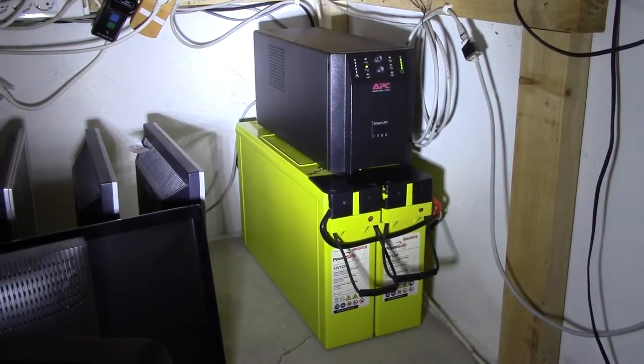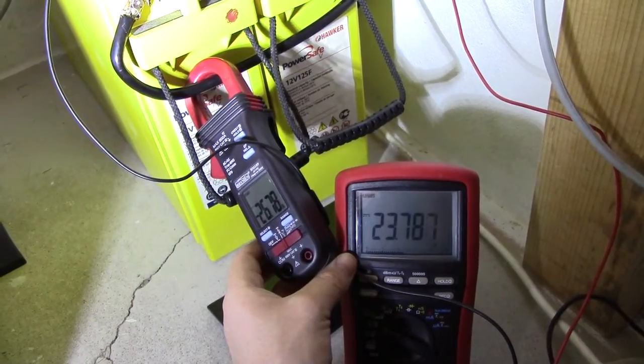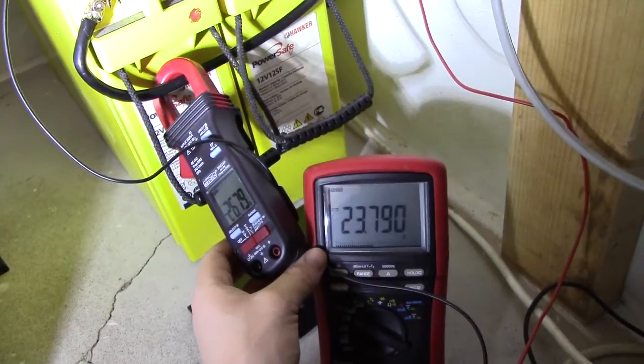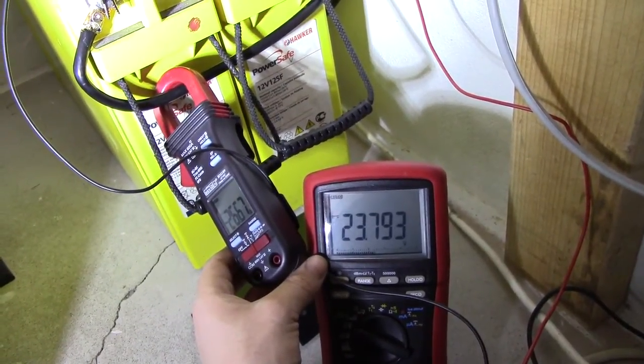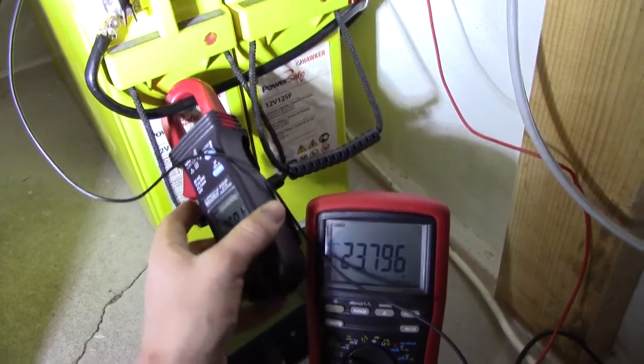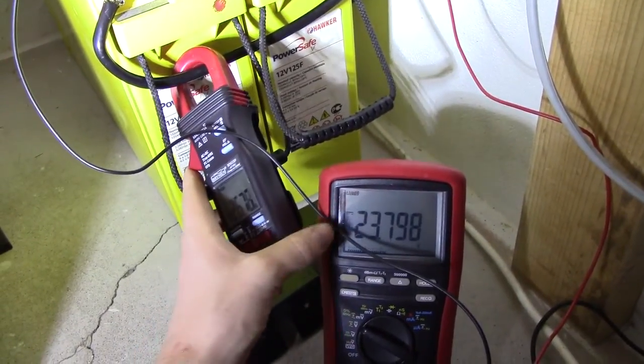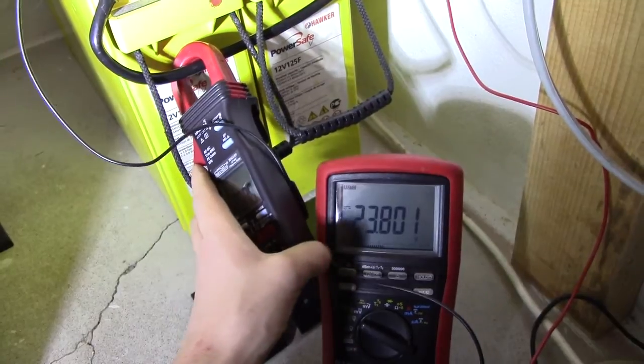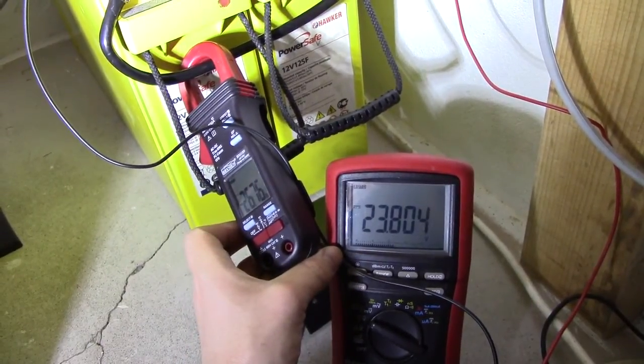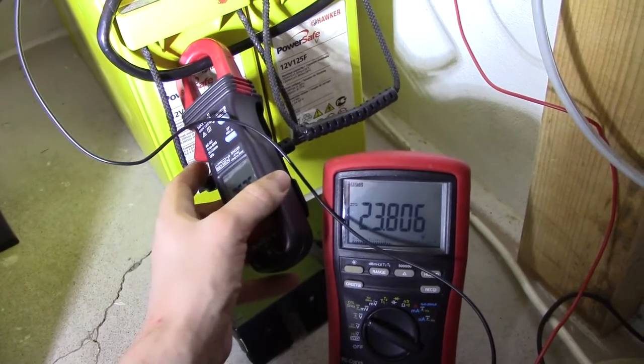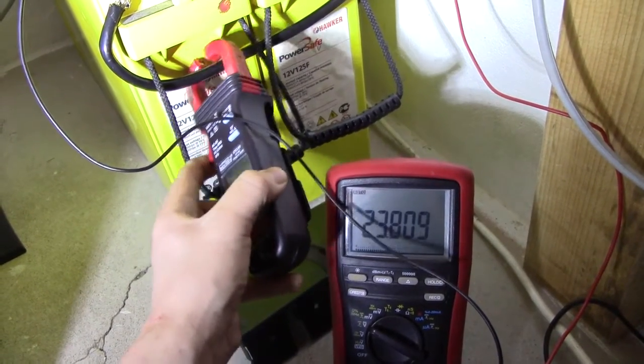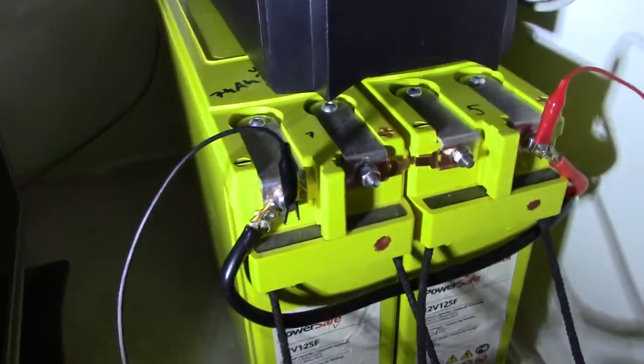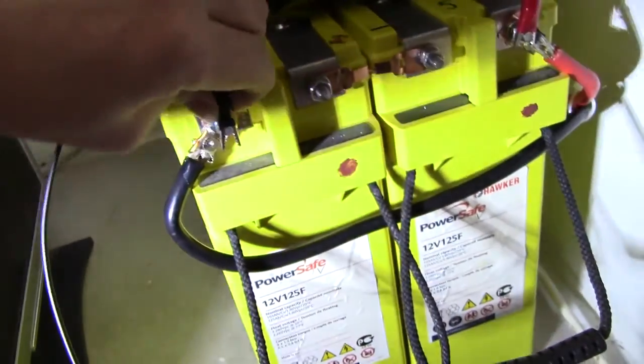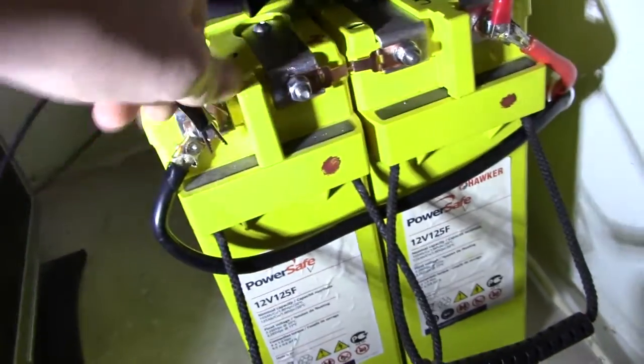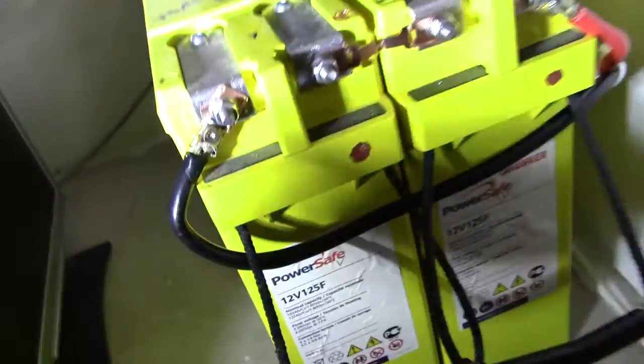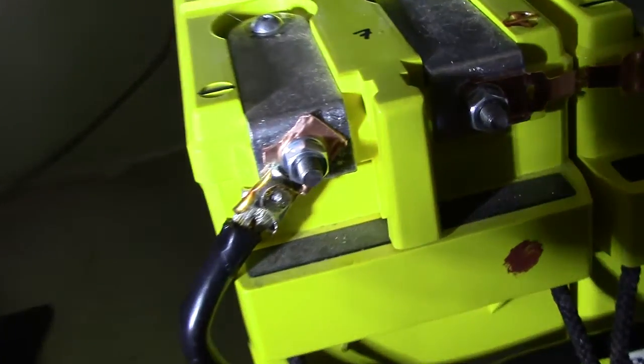And it's pretty. And we have a self-test going at 27 amps and 23.8 volts. So this should take a couple of hours to complete, and the battery voltage is going up even under almost 30 amps of load. That's more than can be said for the old batteries. Now you can also see my absolutely horrible homemade connections in lack of better alternatives.